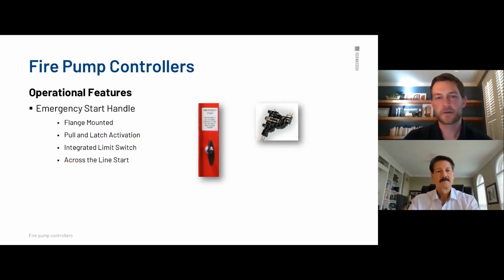And that is always going to be an across the line start. So even if you have a soft start or a Y-delta closed transition or part winding or whatever your starting method, if you have a reduced voltage start, when you pull the emergency handle, it's going to bypass that. You're pulling the power straight into the motor contactor. So we're skipping all that other stuff and going straight from the power source into the motor contactor to start the pump and the motor. That's always going to be across the line. So if you have a big 500 horsepower motor, it's still going to be across the line. It can be a huge spike in amperage. So again, it's an emergency handle. It's obviously the worst case scenario if you can't get your pump started.